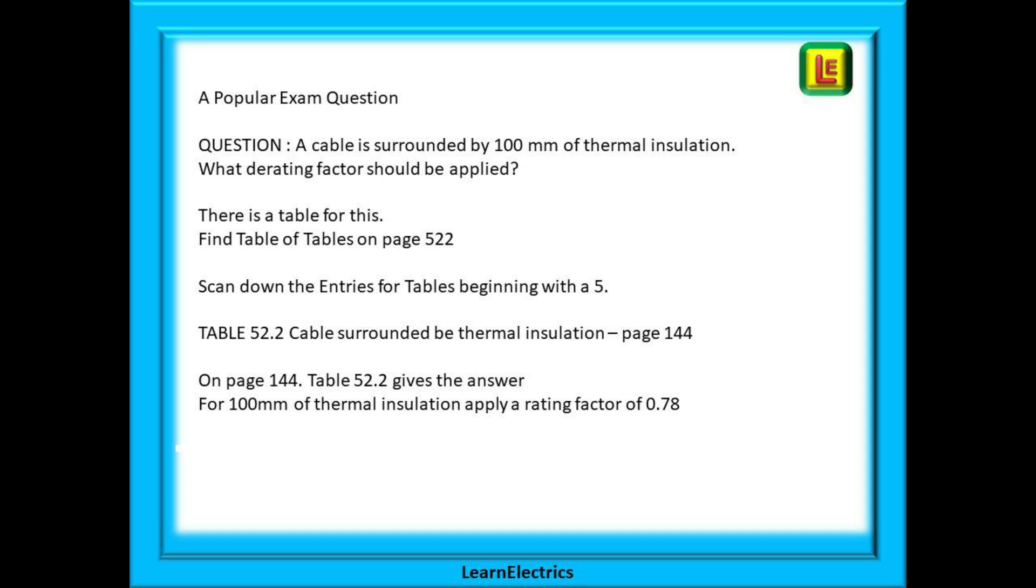Find table of tables on page 522. Scan down the entries for the tables that begin with a 5. Table 52.2 says cable surrounded by thermal insulation page 144. On page 144 table 52.2 gives the answer. For 100 millimeters of thermal insulation apply a derating factor of 0.78.